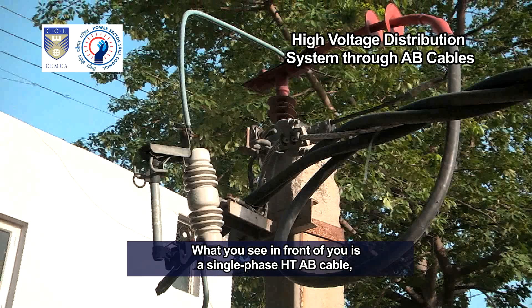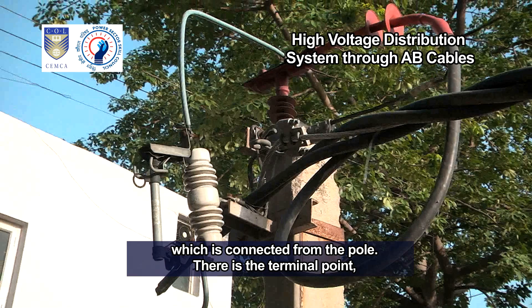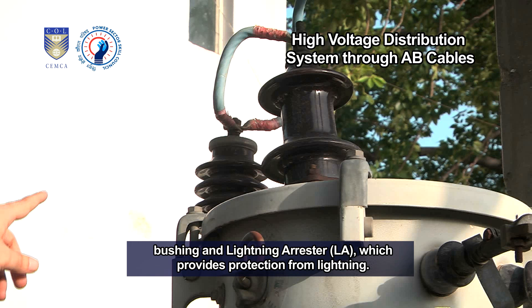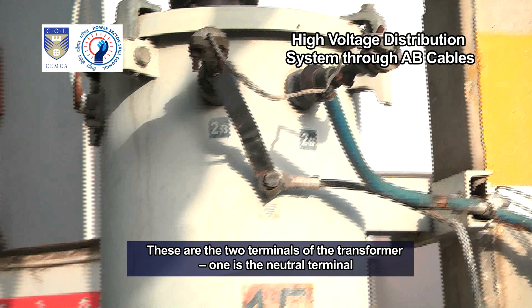The distribution transformer is installed at the doorstep of the consumer to step down voltage to a usable level. What you see in front of you is a single phase HT AB cable, which is connected from the pole. There is a terminal point, which is connected through a DO fuse, distribution transformer bushing, and lightning arrester, LA, which provides protection from lightning.